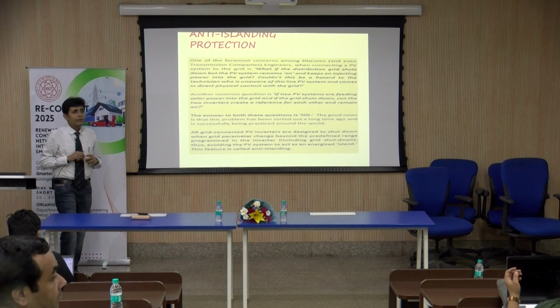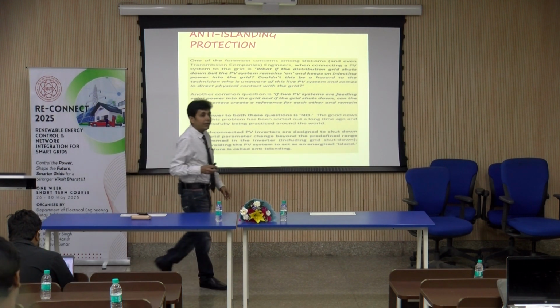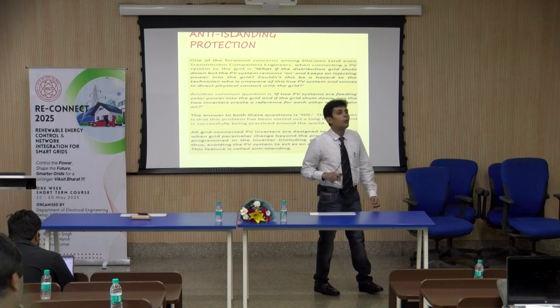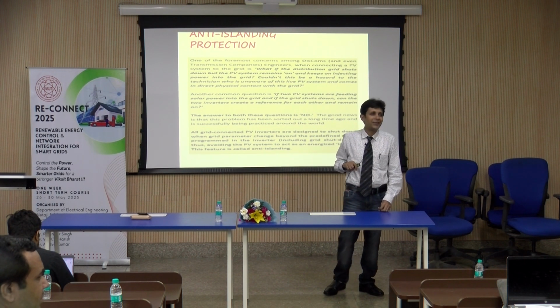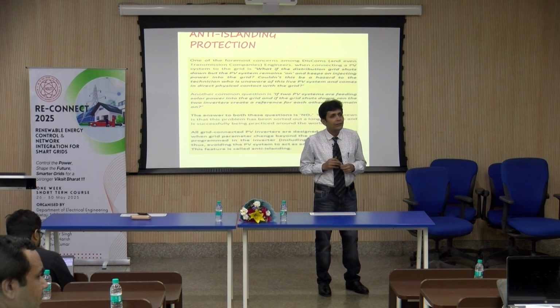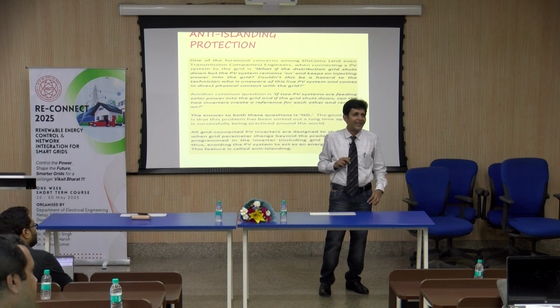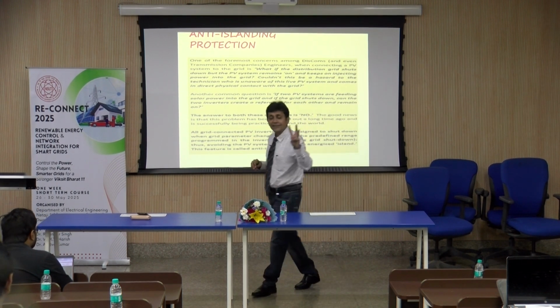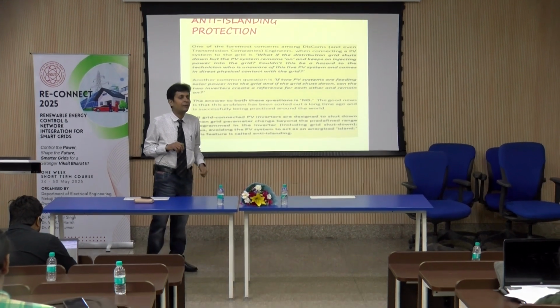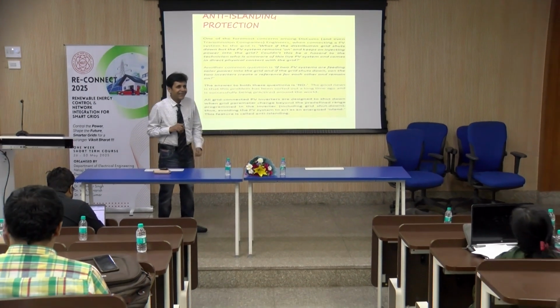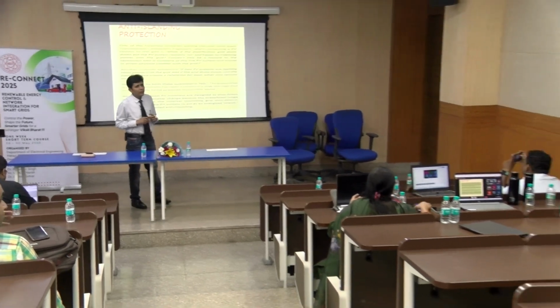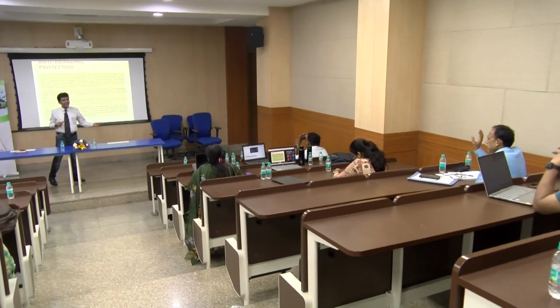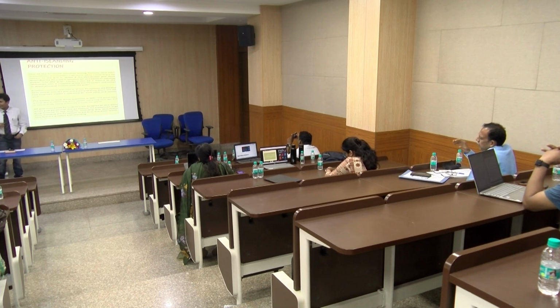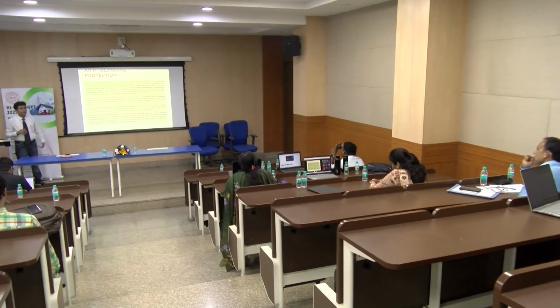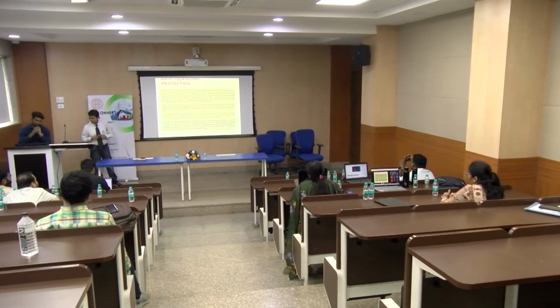Could you please explain again? It's not clear. Anti-islanding means islanding is not allowed. Islanding is not allowed, but then you are generating at the solar end, no? No, it will stop automatically. It senses through two parameters, primarily frequency and voltage. So if the grid frequency and voltage are not there, it should stop. It will stop, definitely. That is called anti-islanding protection. It will stop generating for that particular period. Synchronization will fail.